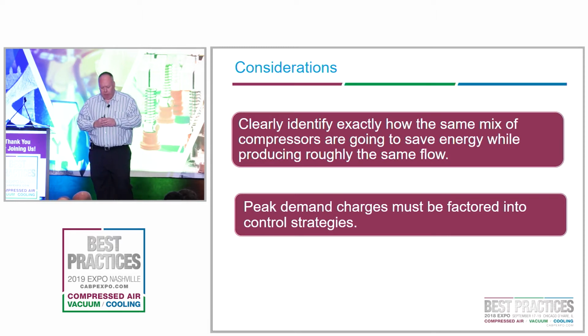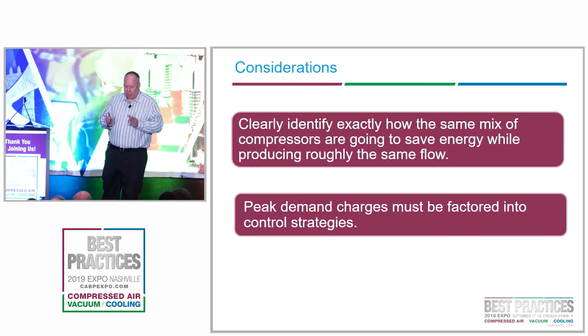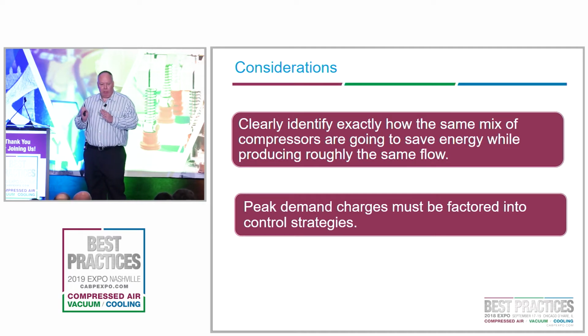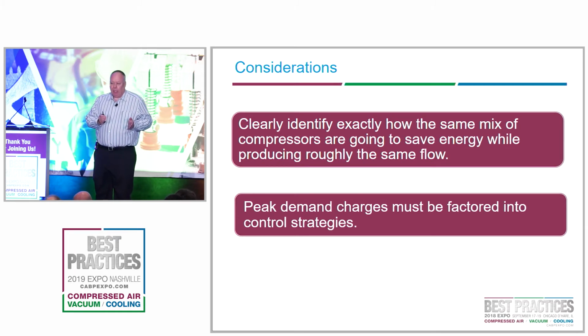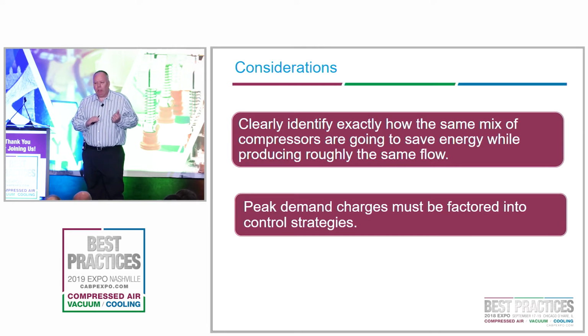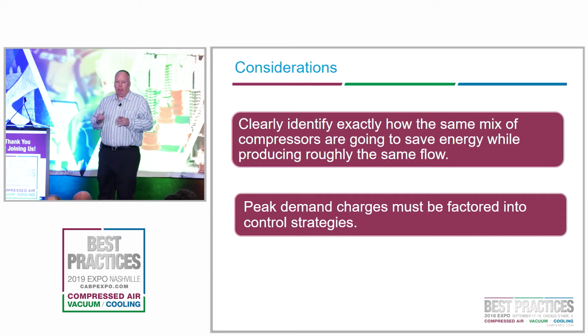Also, something we're seeing more and more in the systems I've looked at recently is demand charges. We've always been told to turn off every compressor we can and only turn one on when needed. But sometimes we're finding that at certain times of day, you're better off leaving one of those compressors running unloaded and letting it load up as needed, because that little window of time when you start a compressor can bump you into another bracket on your energy bill.